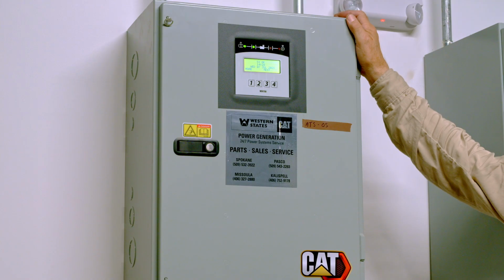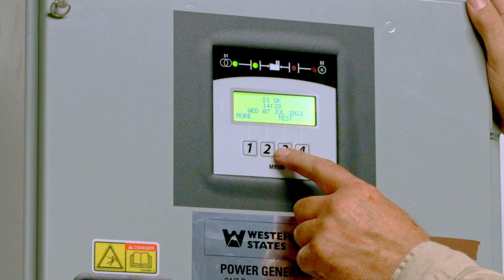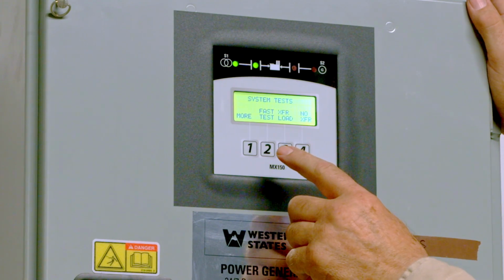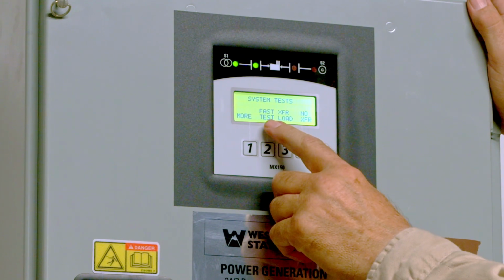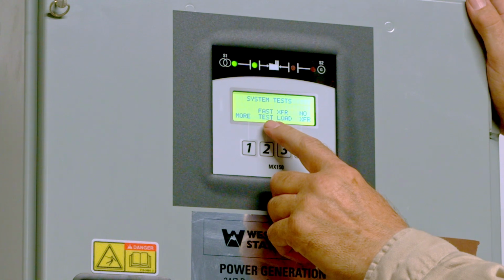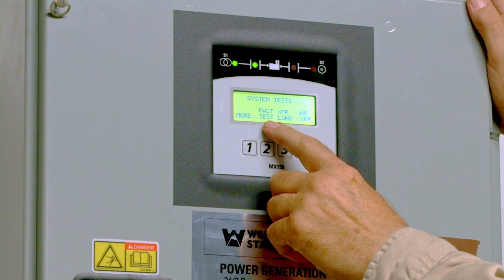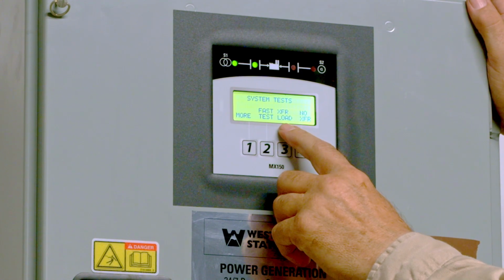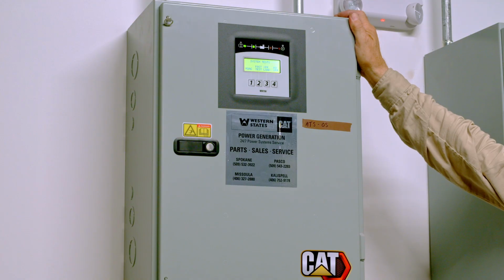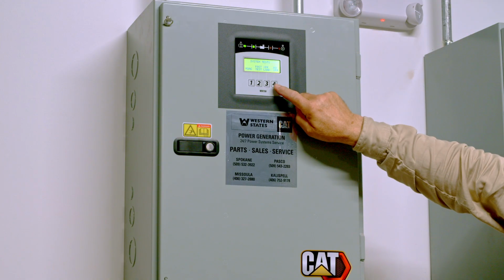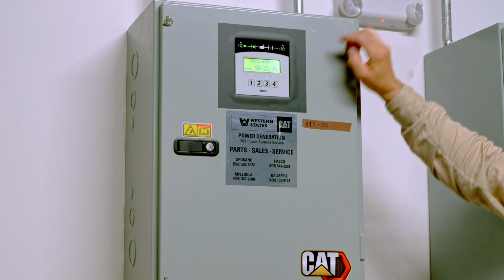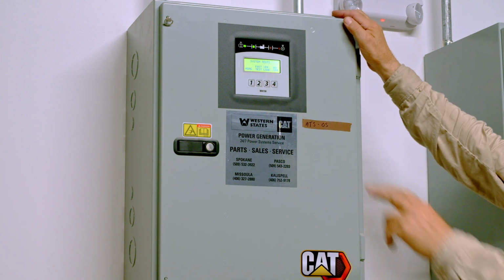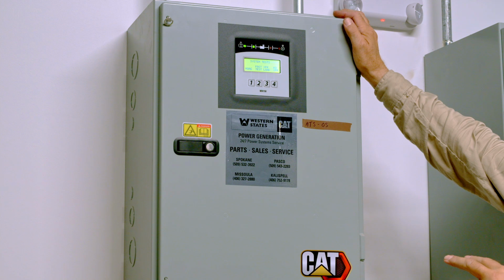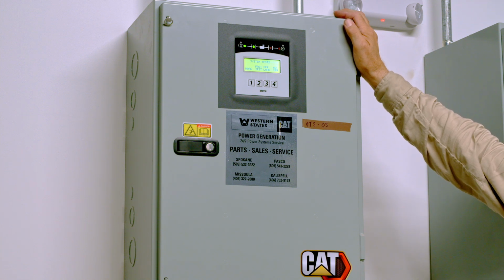To do a test, won't do it right now, but you push the test button, and a fast test, as long as you hold the button, the switch is transferred to generator. Transfer load will transfer it, and you'll have a return to normal time delay of 30 minutes before it returns. No-transfer just starts the generator. These two where it transfers, you have to hold them till it transfers. If you let go, the cooldown timer will come into play and it will not transfer.